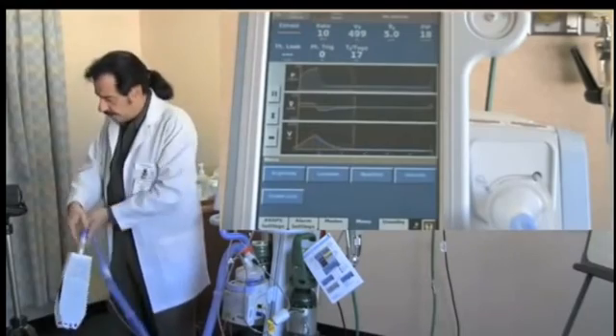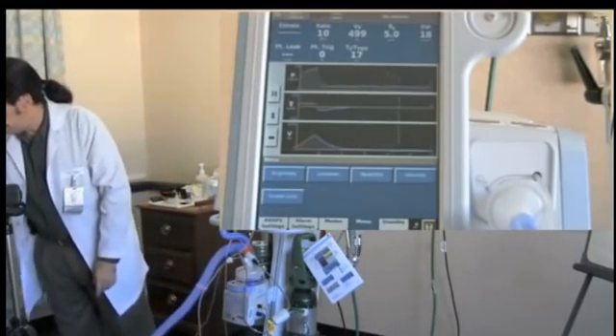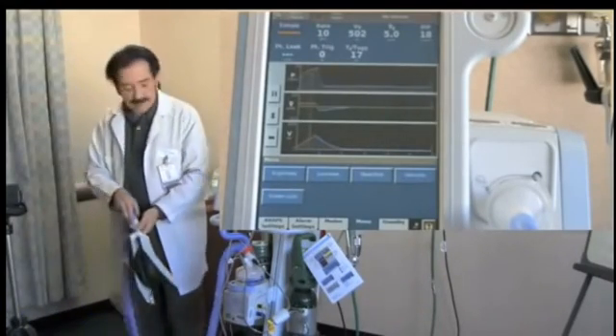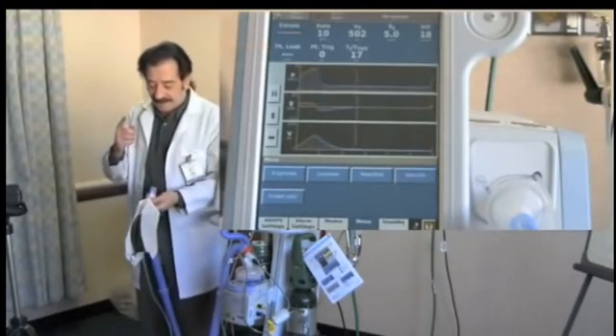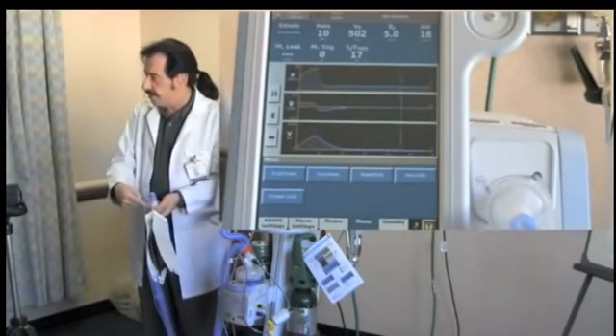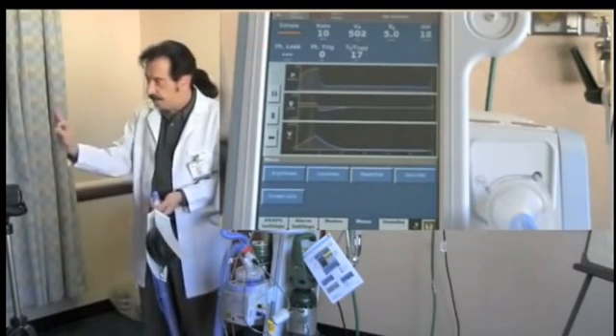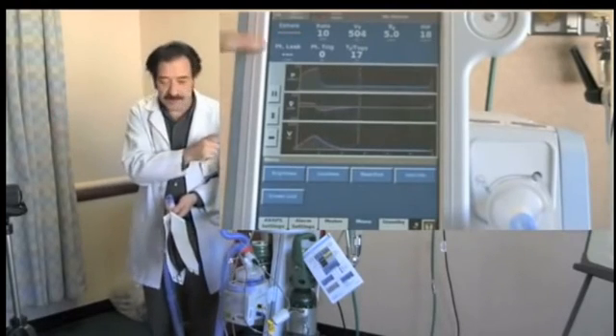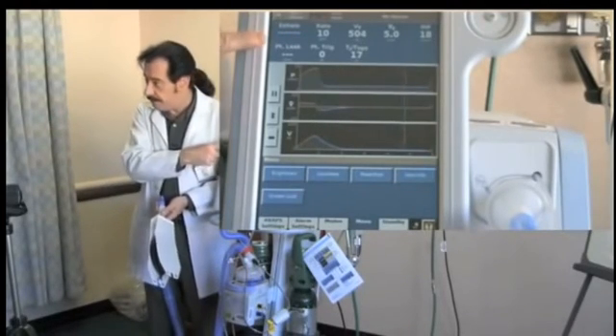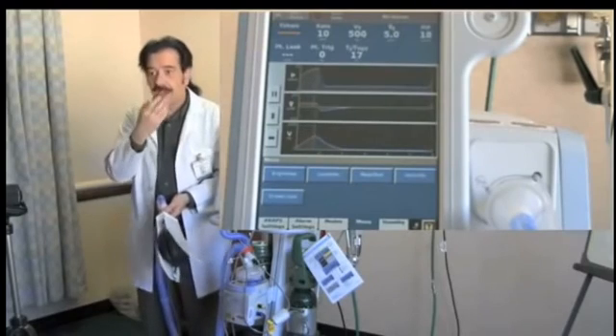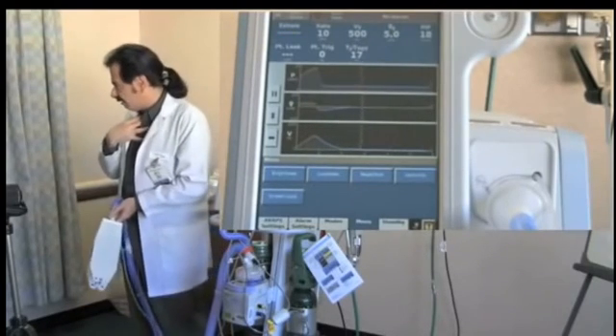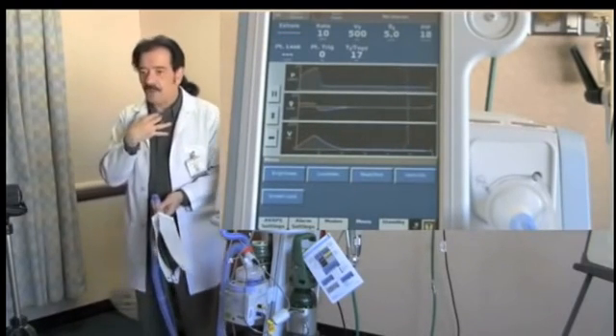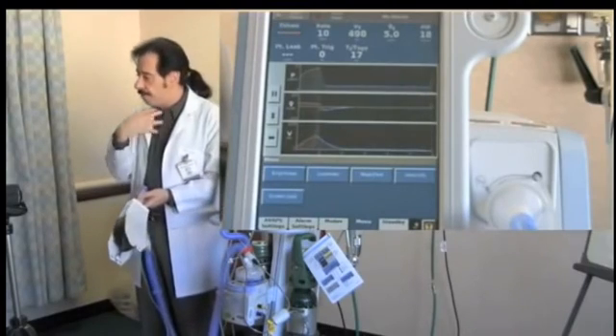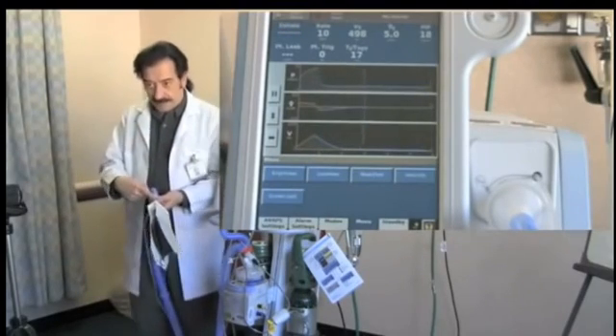Well, can you feel a leak there? I can hear a leak there. There's a leak there. Why is it saying 0? Well, what the V60 is saying is, I know what this leak is, so I'm baselining it. And I'm zeroing that out. So now whatever leak you see here must be coming from the patient. The nasal mask isn't on tight, or their tracheostomy tube is a little leaky, okay? And so whatever leak I report is coming out of the patient, not out of the whisper valve, okay?